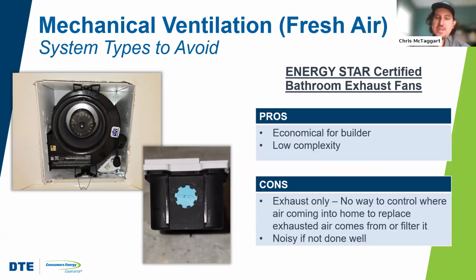Exhaust-only ventilation is pretty economical. It's easy to get right, meaning it's easy to set it up right. The challenge is that you don't know where the air is coming from. So it can be coming from gaps and cracks in our building envelope adjacent to attics, crawl spaces, etc. And it can be noisy if it's not done well, but obviously if you choose an Energy Star bath fan, not only are they energy efficient, but they're also quiet.